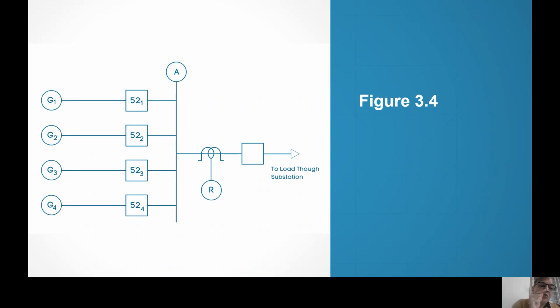So at night time, say you have to make G1 and G2 off, and G3 and G4 will run. Now when G3 and G4 run, obviously the current passing through the primary of relay R will be less. So the plug setting required for relay R is different at night. At daytime it is different. At night time, the plug setting is different. Two different plug settings are required, right? At daytime different, at night time different.